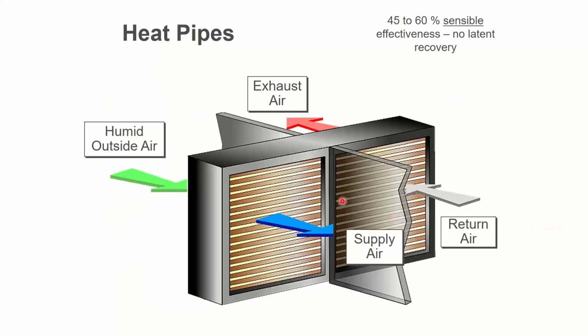Heat pipes is kind of similar, but instead of water in there, you have refrigerant. So now it's not going to work for long distances. It only works for small stuff, really close to two airstreams that are near each other. But I have refrigerant in these pipes. There's no compression in this discussion, just refrigerant in the pipes. And inside the pipes, I'm going to evaporate refrigerant on one side. It's going to migrate to the other and condense and have like a little mini refrigeration cycle in between them. But once again, it doesn't get low enough to hit the dew point of the air, so it doesn't do any latent work. It only does sensible, hence it doesn't comply with code.